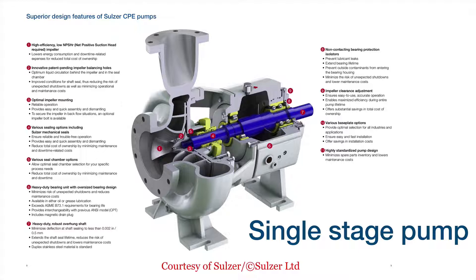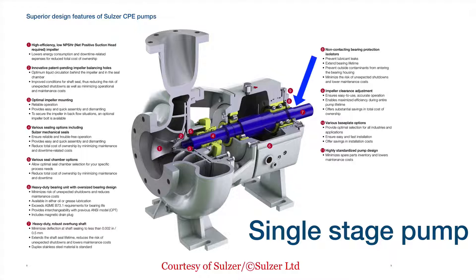This is a single-stage pump. Here we have the stationary part — the casing, the volute. The fluid enters the pump through the impeller eye here, and this is the pump suction flange to connect the suction pipe to the pump. The fluid passes through the impeller and exits radially to the shaft. The main rotating element is the shaft, and at the end of the shaft the impeller is affixed. The impeller has many blades to convey the fluid from the suction to the discharge, transmitting energy to the fluid.